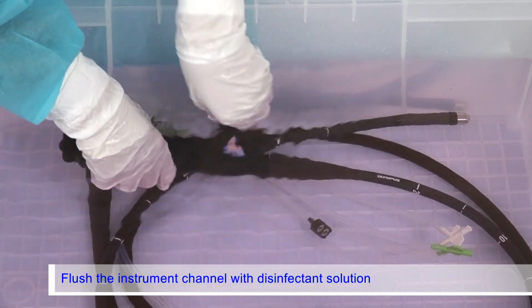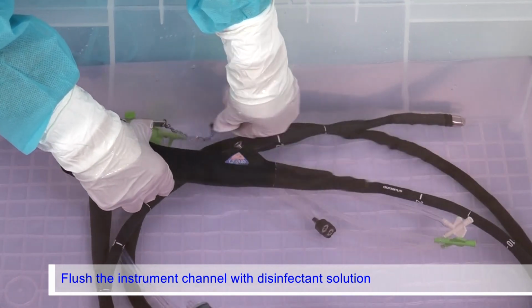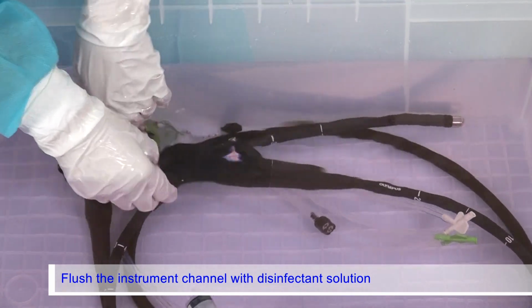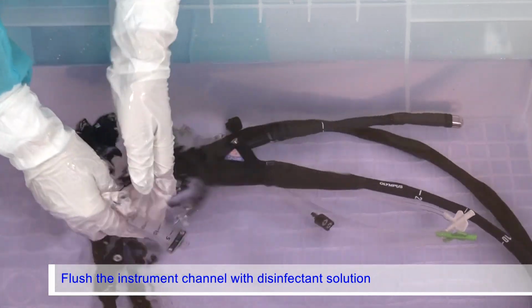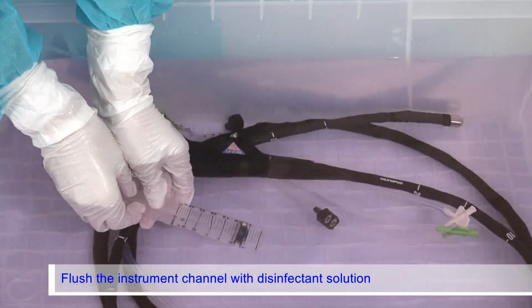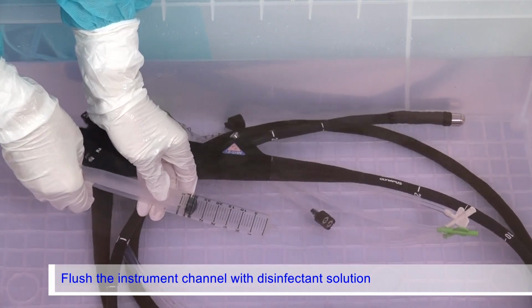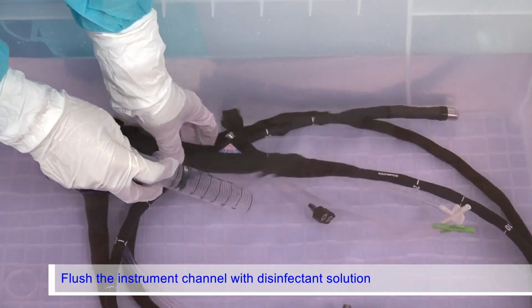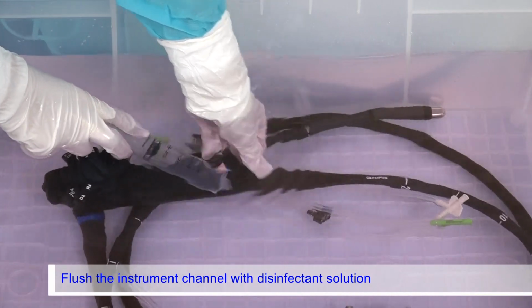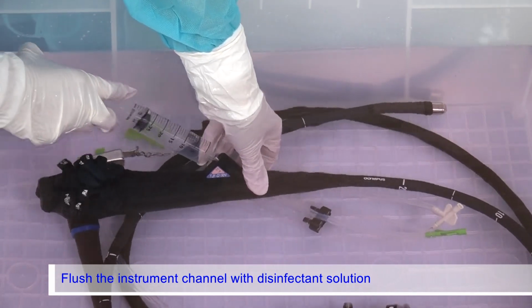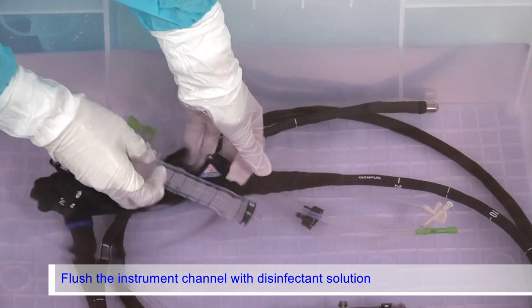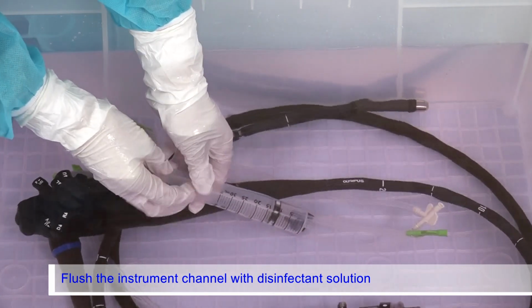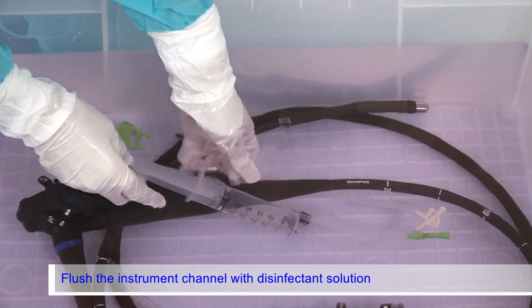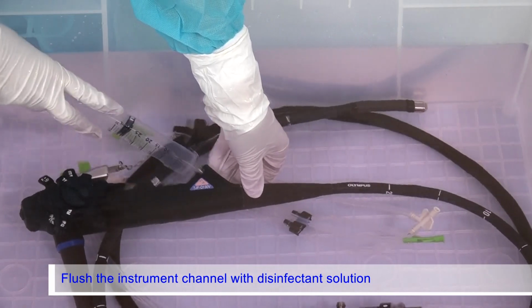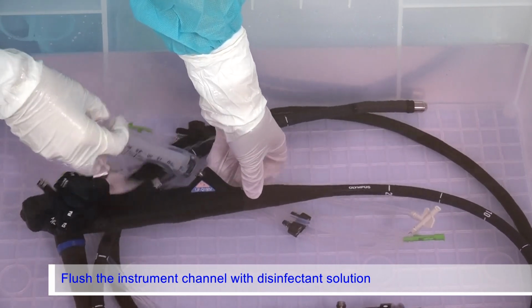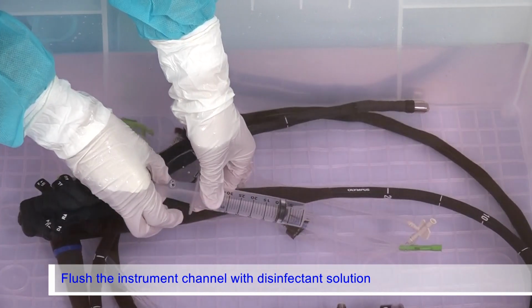While immersing the endoscope completely in the disinfectant solution, remove the biopsy valve cap of the channel plug from the instrument channel port. Slowly fill the syringe with the disinfectant solution. Put the distal end of the syringe in the instrument channel port. Then, forcefully flush the instrument channel with 30 milliliters of the disinfectant solution, minimizing disinfectant solution leakage from the port. Repeat the step 5 more times.